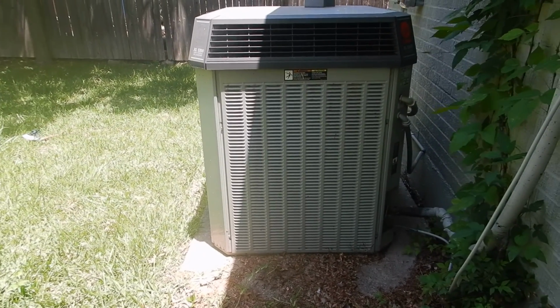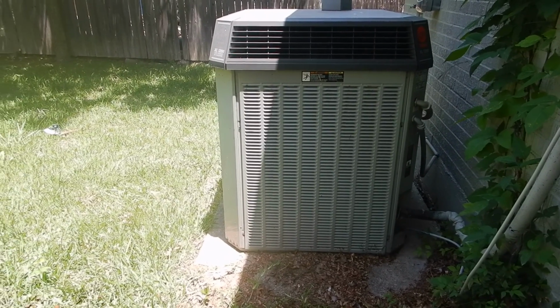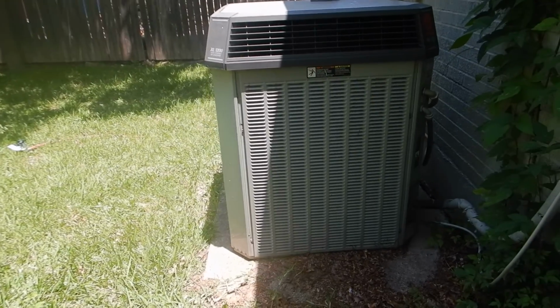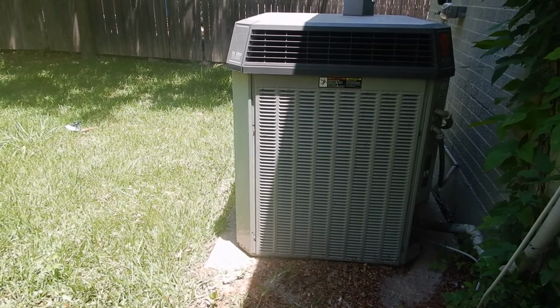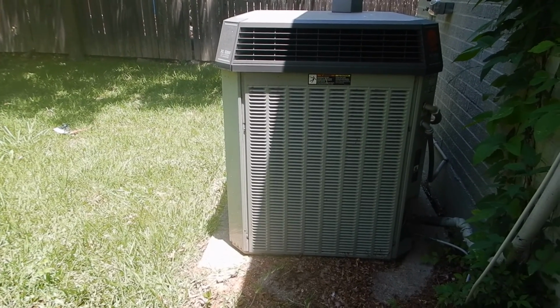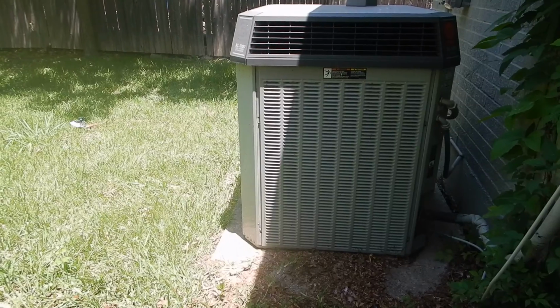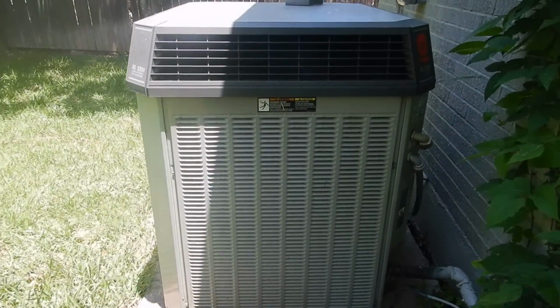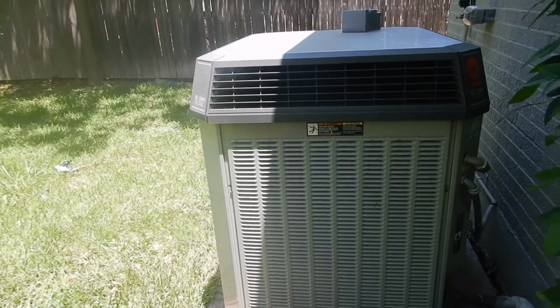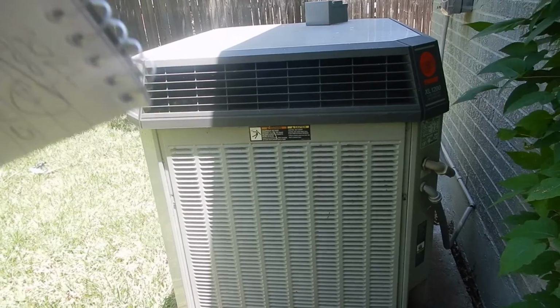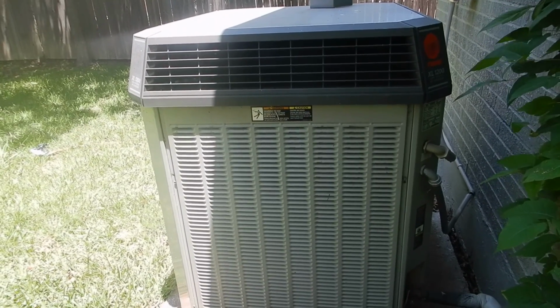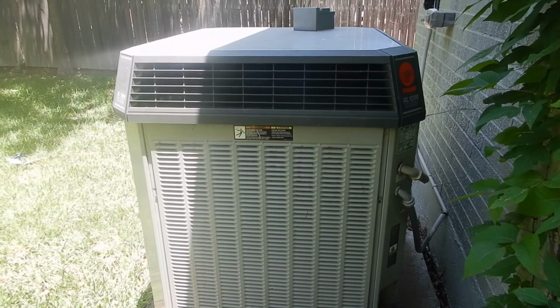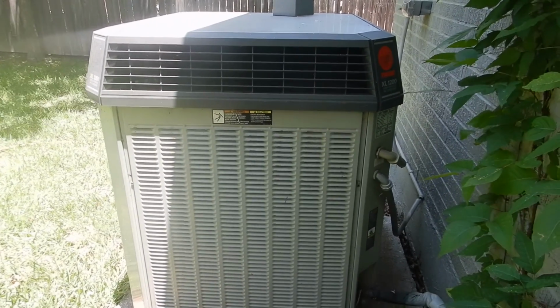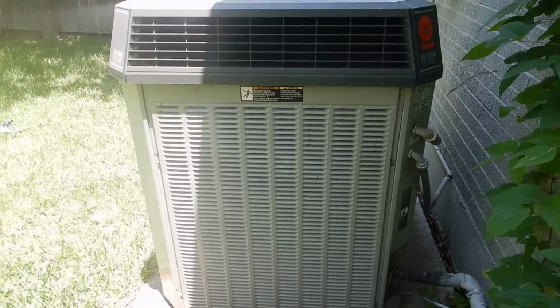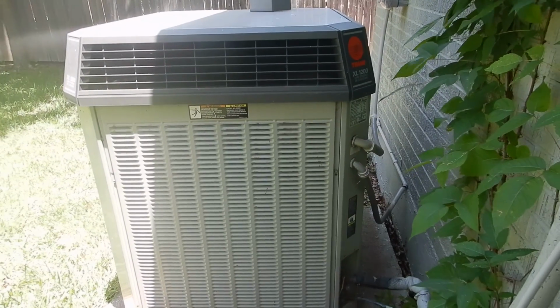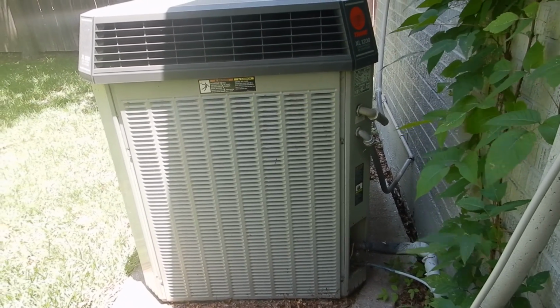And if a technician convinces you to put in a drop-in, an alternative refrigerant, then you might as well put him on payroll, because nobody's going to want to follow that air conditioning guy. So this system is over 14 years old, it uses R22, and it's got a low SEER rating. It's also overfused. It's a 40 amp fuse in the electric service panel, and the maximum fuse for this unit is 35. That means two things. One is that this system could fail before the circuit breaker trips. It's only 5 amps, but it could fail before the circuit breaker trips to save it. And you're probably going to have to undersize the circuit breaker when you do replace this thing, and it would be prudent to budget for replacement. It's time.